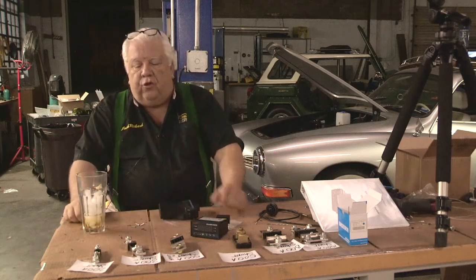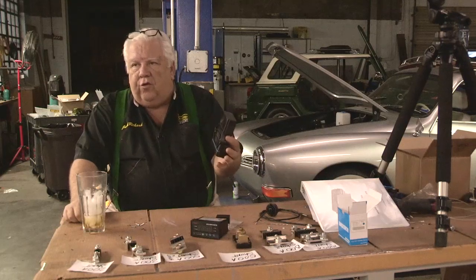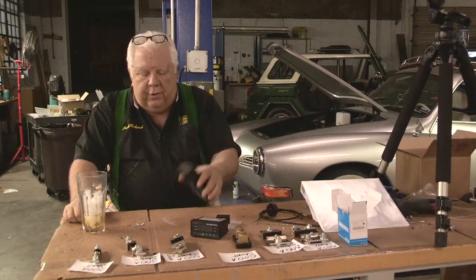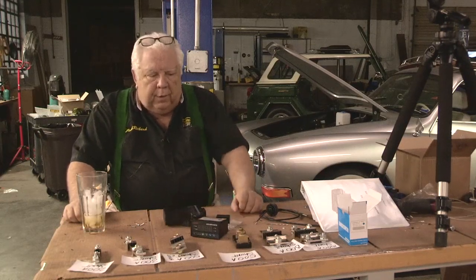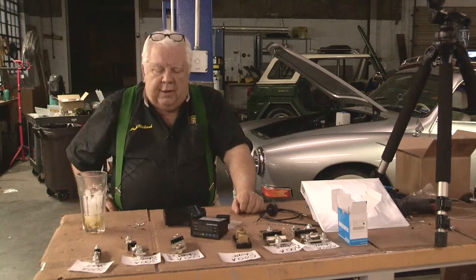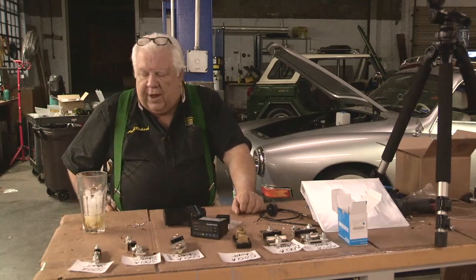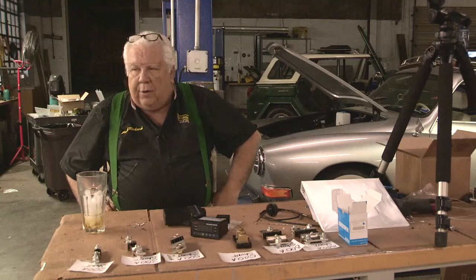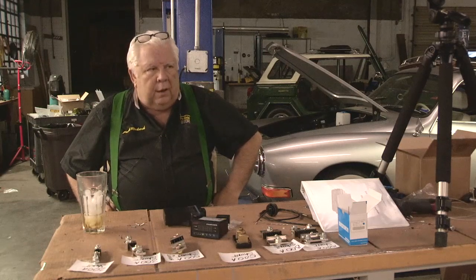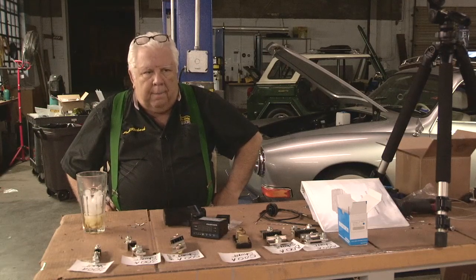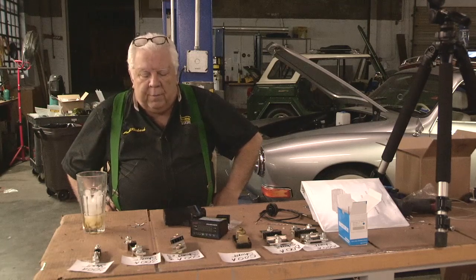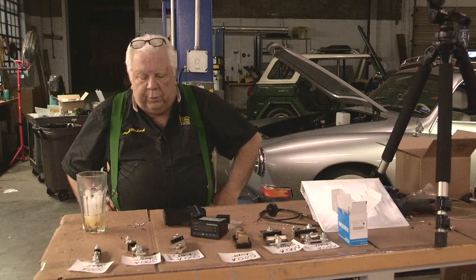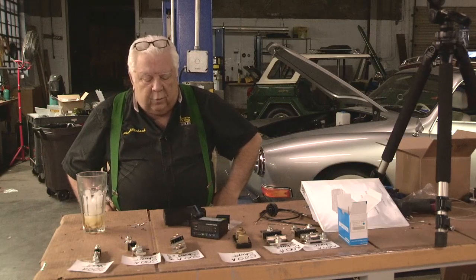And number three, this should be at least two orders of magnitude more accurate than what's reported by the inverter. The level of accuracy the inverter needs on battery voltage and current to properly invert and drive a motor is pretty minimal. This will be much better. And so CAN bus is the way we will report that.